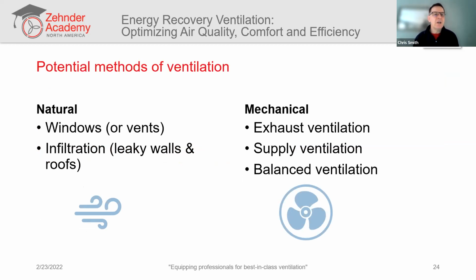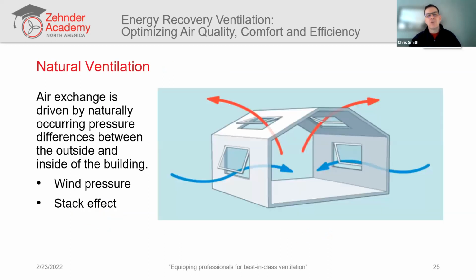Natural ventilation could be done with windows or maybe some vents, or more likely it's done just by infiltration. Infiltration basically amounts to leaky walls and leaky roofs. Mechanical ventilation is ventilation that's controlled with fans, a fan or fans. Could be exhaust ventilation, could be supply ventilation, or it could be a combination, exhaust and supply done in a balanced way, balanced ventilation. So let's look at natural ventilation.